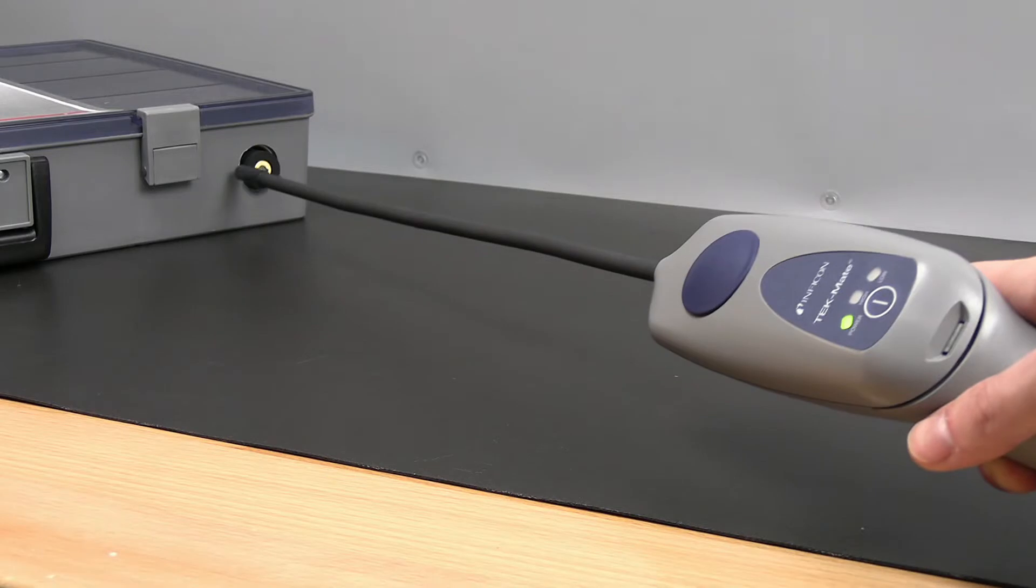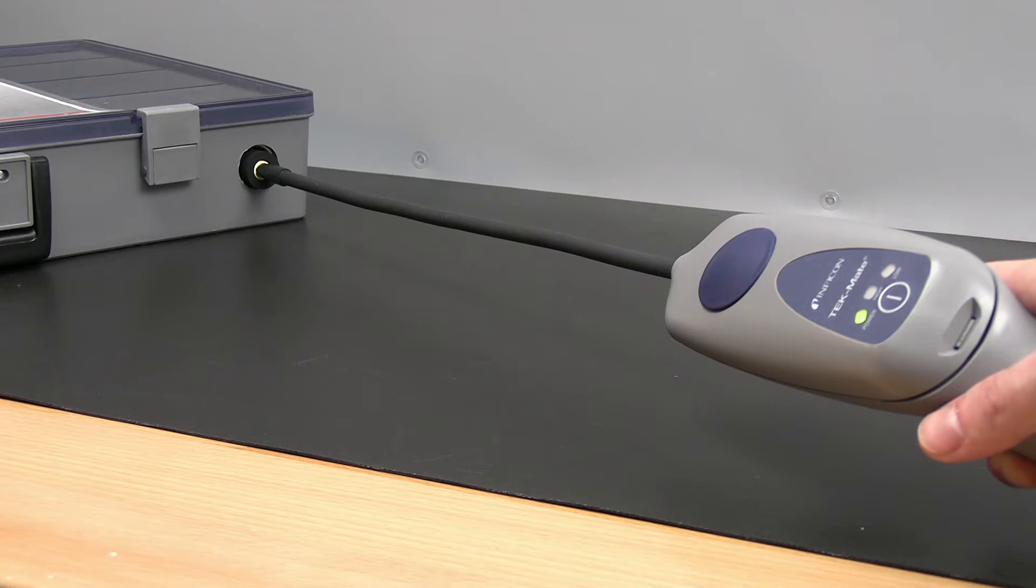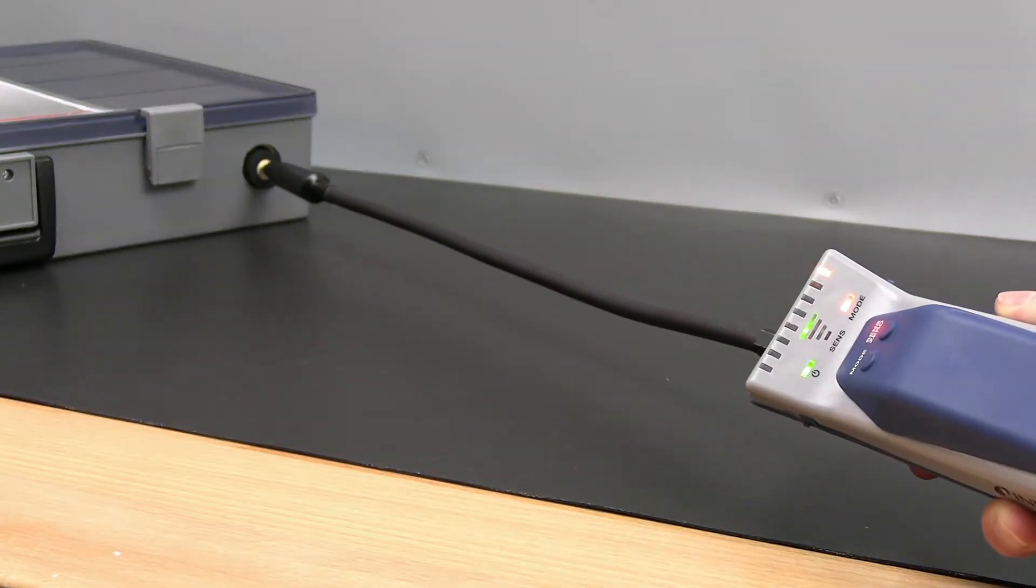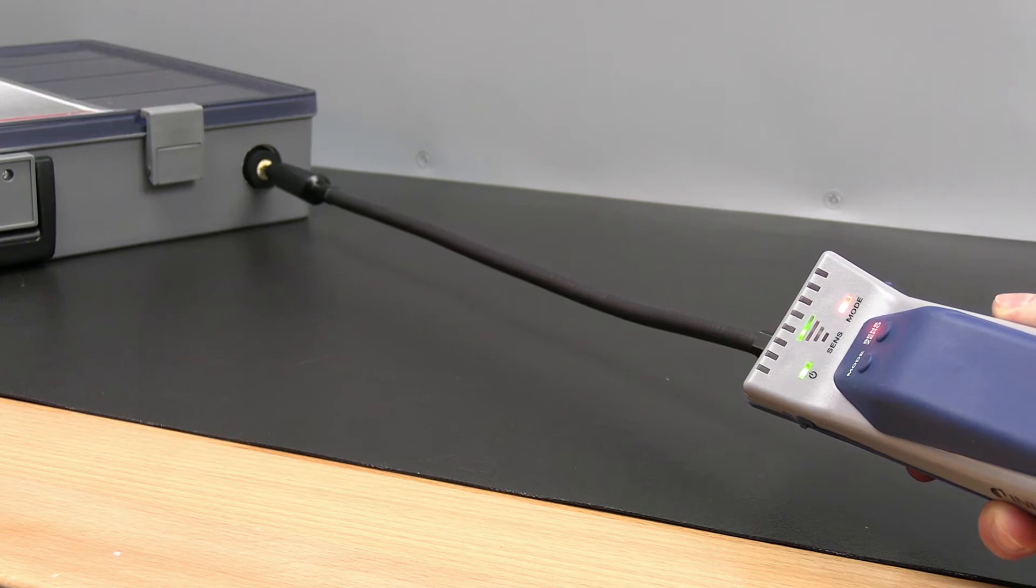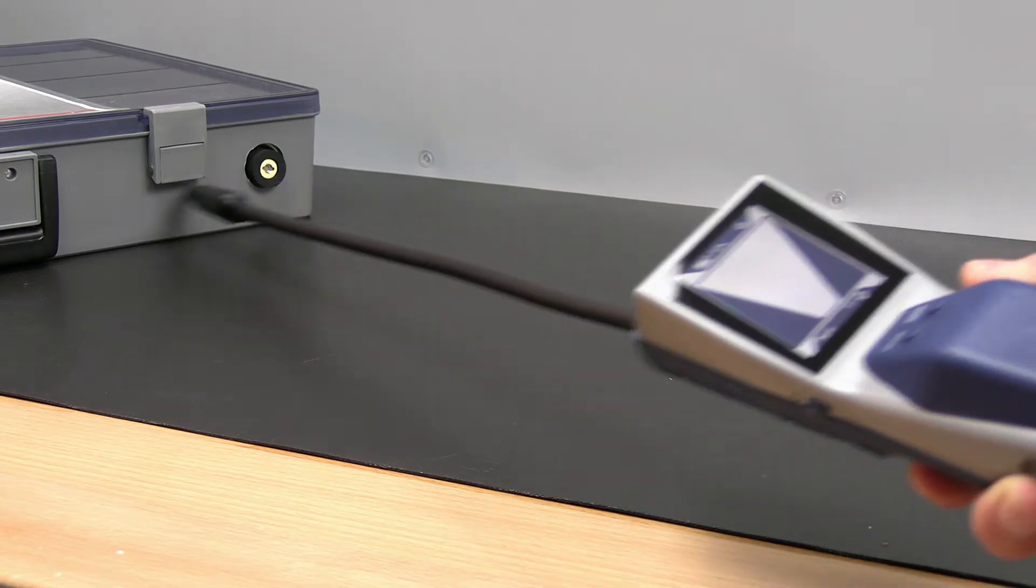In Pinpoint Mode, every couple of seconds the leak detector will automatically zero to the background refrigerant concentration. And when this occurs, either continue looking for a higher concentration of refrigerant or move to an area of lower concentration to reset that zero point.